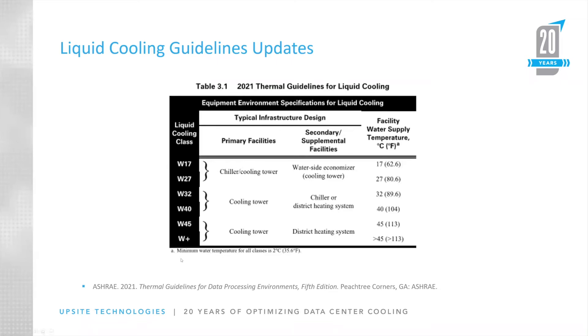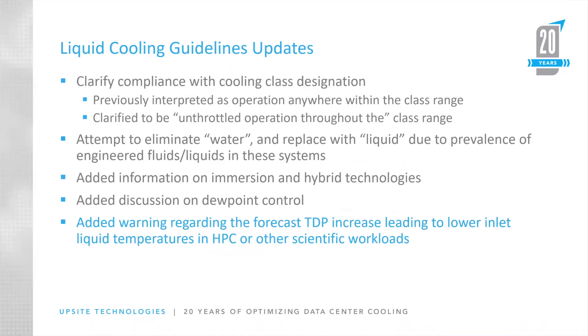The minimum water temperature for all these classes is 2 degrees centigrade. When designing for this, you have to be careful — while IT systems can technically operate that cold, if you have a controls failure you need to consider condensation on your piping. This scenario isn't really a continuous operating condition; it's one where the system has been offline for major maintenance, repair, or installation and you're doing a cold startup without heat already in the cooler.